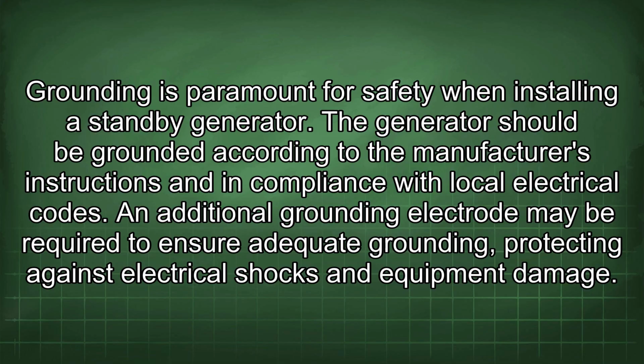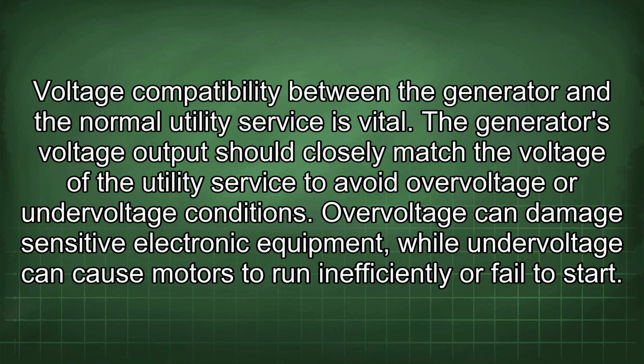The generator should be grounded according to the manufacturer's instructions and in compliance with local electrical codes. An additional grounding electrode may be required to ensure adequate grounding, protecting against electrical shocks and equipment damage. Voltage compatibility between the generator and the normal utility service is vital. The generator's voltage output should closely match the voltage of the utility service to avoid overvoltage or undervoltage conditions. Overvoltage can damage sensitive electronic equipment, while undervoltage can cause motors to run inefficiently or fail to start.